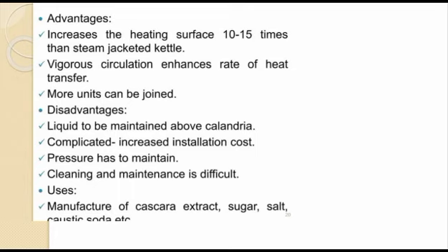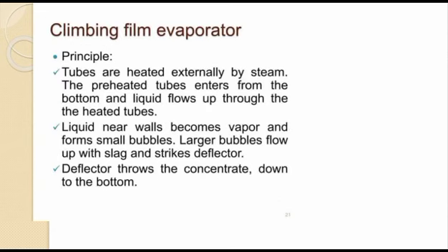Advantage: it increases the heating surface 10 to 15 times more than a steam jacket kettle. Disadvantage: the liquid level has to be maintained above the calandria, pressure has to be maintained, and cleaning and maintenance is difficult. Uses: manufacture of extracts, sugar, salt.